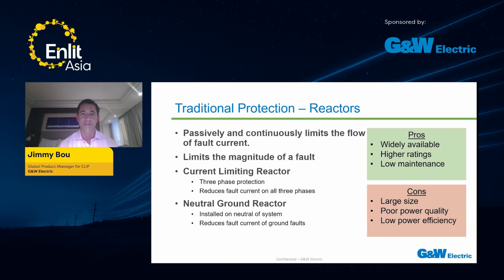as the vast majority of the audience here in this webinar. These ones do not interrupt time, they only do magnitude, and they're constantly limiting such magnitude. Two examples of these are current limiting reactors, three-phase protection, and then you got your neutral ground reactors, which, just like the name states, reduces fault currents at ground faults, right?